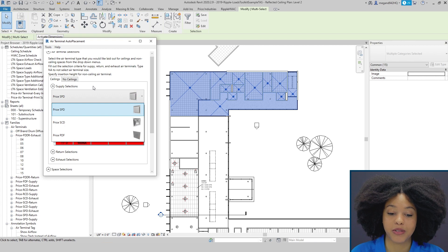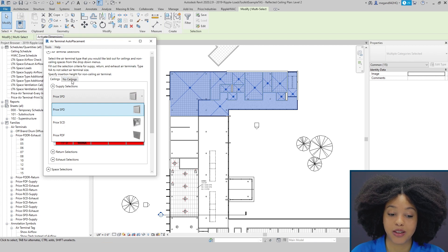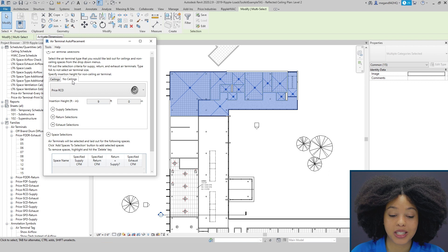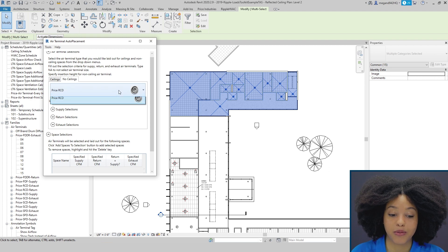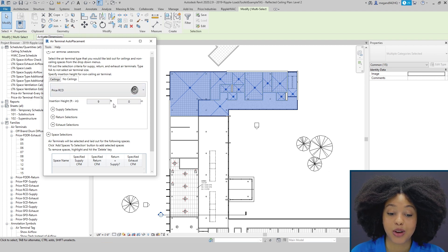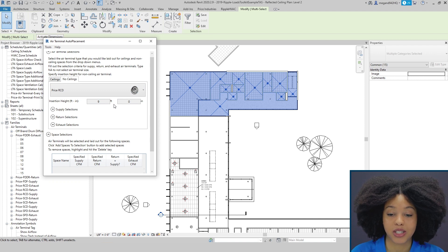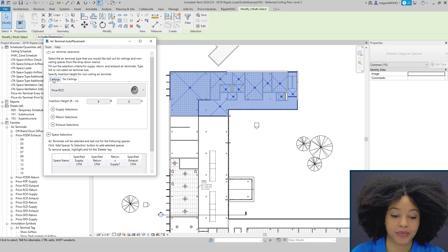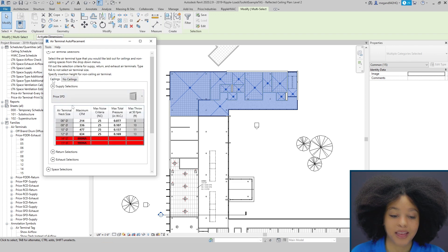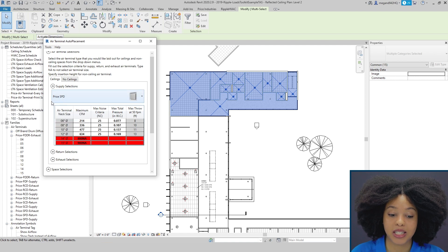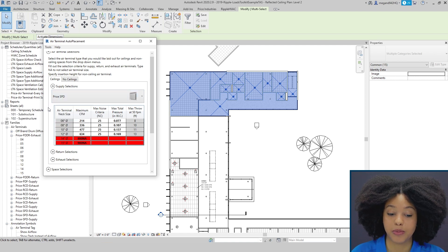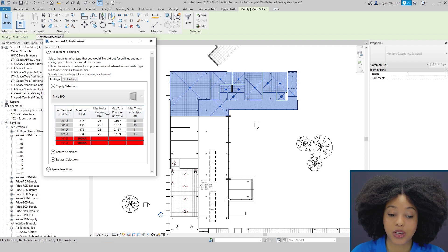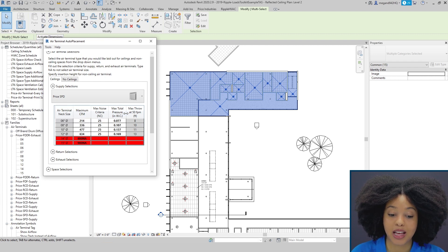You can also specify the type of diffusers for a ceiling versus no ceiling application. For no ceiling applications, we have the option of the round cone diffuser, and you can also specify your insertion height so Revit knows where to insert the diffuser. Within the selection, you can also specify some performance limitations. Here you'll see the option to specify your max CFM per diffuser size, your max noise criteria, as well as your max total pressure.